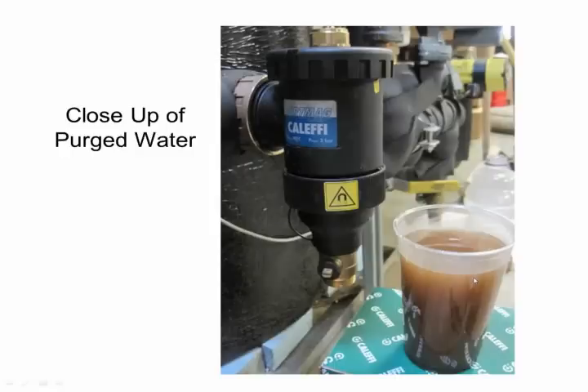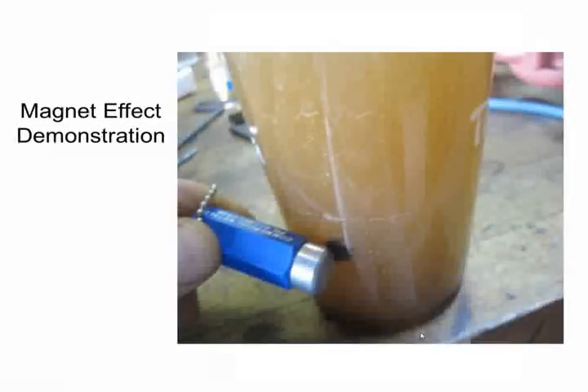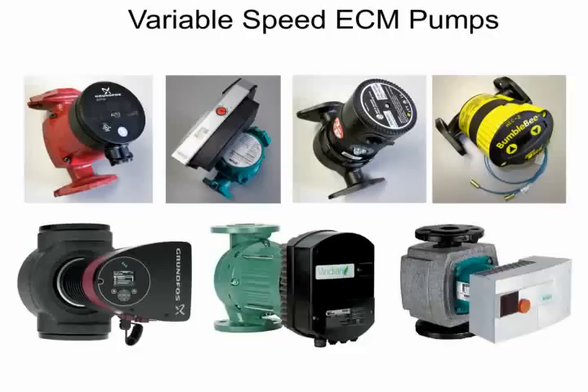And filling up that glass with what you can see is very untasty looking water. And he let the debris settle out, and he put a magnet to the side of the glass. In the next slide, we can see what happened. As he puts the magnet into the glass, the ferrous oxide jumps to the magnet. So that's the effect that we're accomplishing by putting these collars on our dirt separators and preventing that debris from getting into other parts of the system and causing problems.